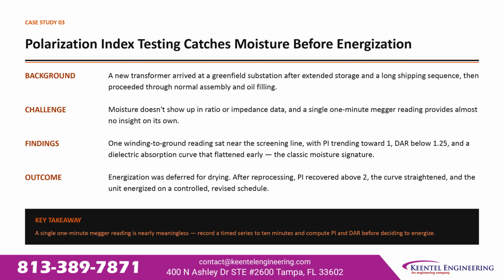Energization was deferred for drying. After reprocessing, polarization index recovered above 2. The curve straightened, and the unit energized on a controlled, revised schedule. The takeaway: a single 1-minute Megger reading is nearly meaningless. Record a timed series to 10 minutes and compute PI and DAR before deciding to energize.